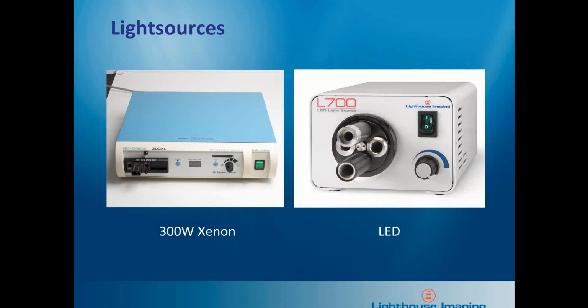So we'll just do a couple of images here of typical light sources. On the left, we'll see a typical 300-watt xenon light source. This is a very common basic style of light source that you'd find in a surgical tower. Each brand has their own different specific look to it, but the 300-watt xenon is kind of the de facto surgical standard. On the right, we'll see Lighthouse's L700 LED light source. More and more, I believe Stryker has gone to primarily LED sources, but still many in the industry are xenons. But definitely the trend is towards the LEDs with a longer life and more stable output.